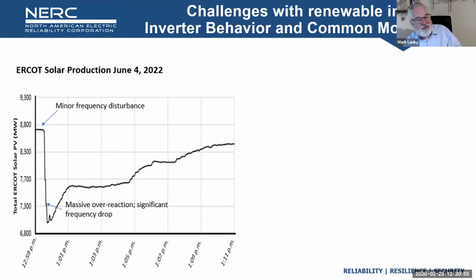What we've seen with inverters is their behavior was, I'll say, disappointing. We had to catch up on it. In California there was a Blue Cut fire where, during a single line to ground fault, we lost 1,500 megawatts of inverter-based resources just like that. They ceased to operate, then waited a while before coming back on, which is also hard to manage. So this idea of riding through events became very important, and we've now written some standards for that.